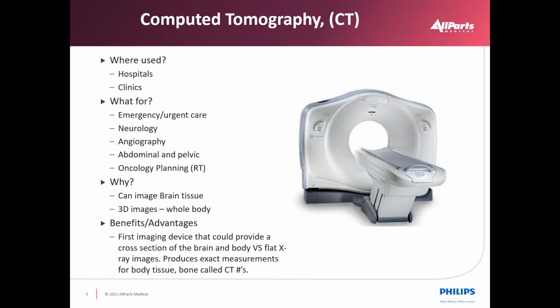The scaling system that we use is that air is -1000, and bone, or calcium, is in the high +900 area, with water being the center of the scale. But it's not any kind of water, it's distilled water. Distilled water, whether it's in Australia, Japan, the United States, Russia, or any other country, will have the same value. It has no mineral content or anything else, it's just pure water. Pure water has a CT number of 0, so that's the center of our scaling system. If you think about it, most of our bodies are made up of water. All the soft tissue is a component of water plus some other item.